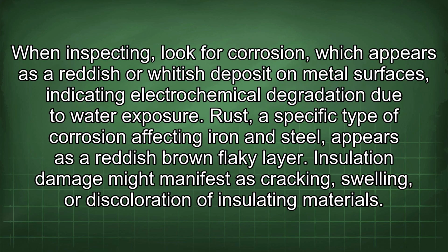When inspecting, look for corrosion, which appears as a reddish or whitish deposit on metal surfaces, indicating electrochemical degradation due to water exposure. Rust, a specific type of corrosion affecting iron and steel, appears as a reddish-brown flaky layer. Insulation damage might manifest as cracking, swelling, or discoloration of insulating materials.